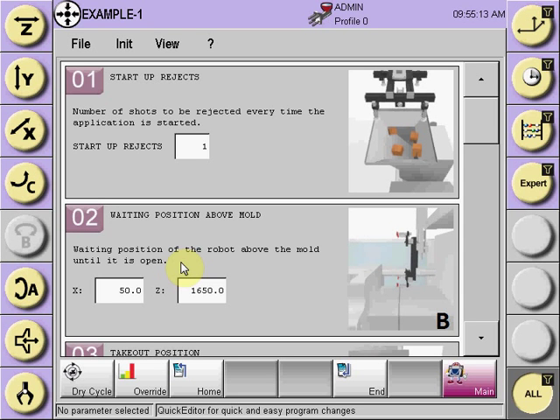Once the Quick Edit program has been taught the positions, time delays, and number of startup rejects — all the informational requirements to run the robot in automatic — prior to putting it into automatic, the program should be dry cycled.